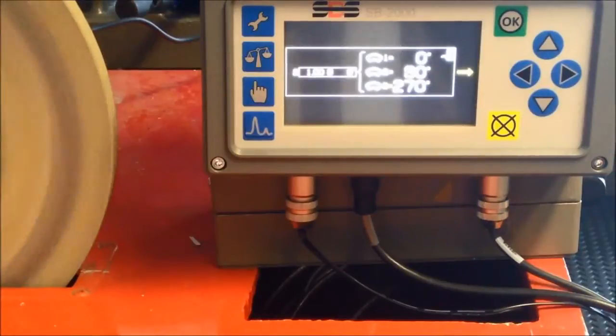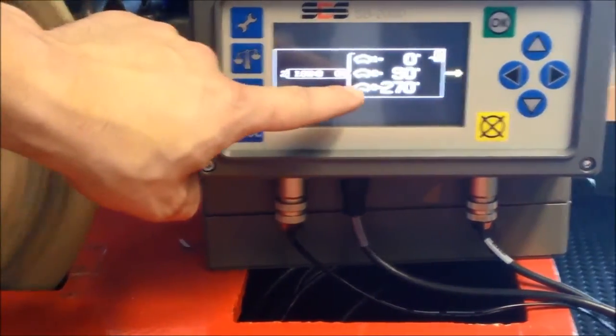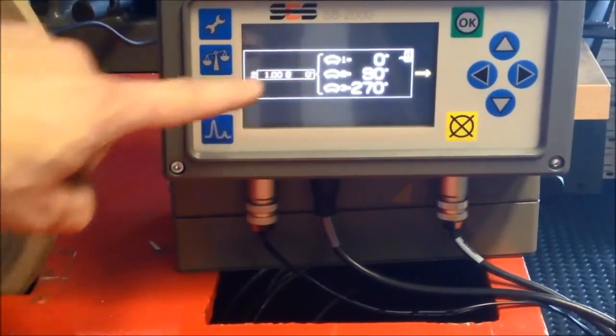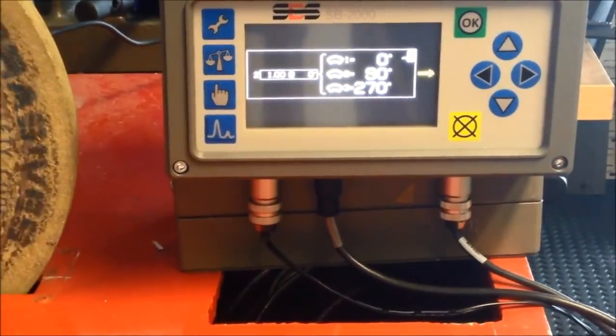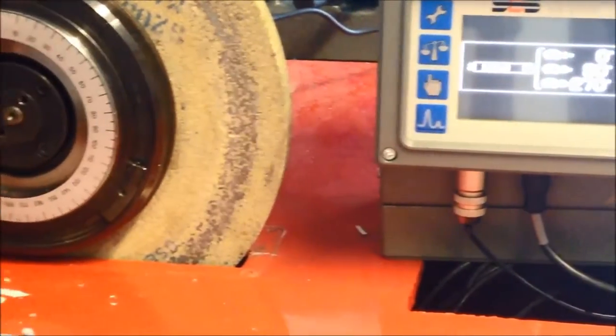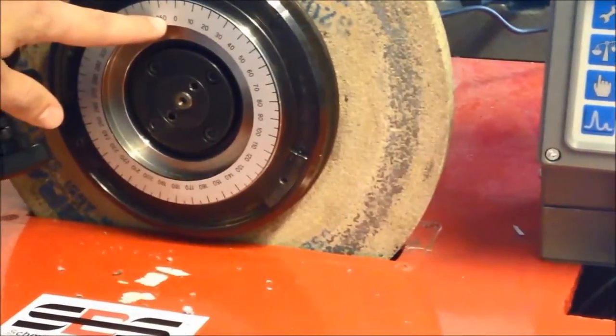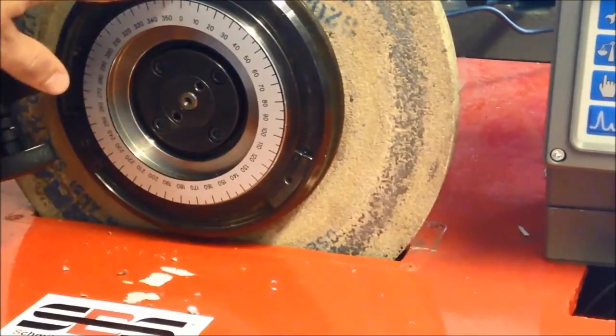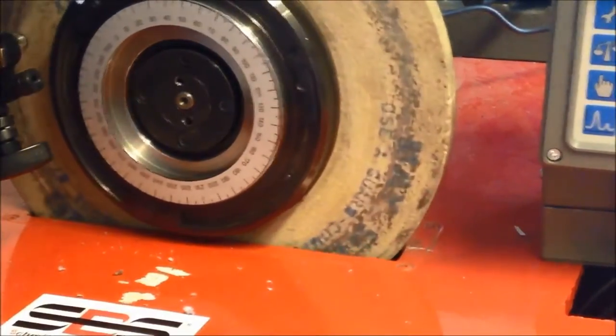Now the test phase. Position the weights at zero, 90, and 270 degrees. As we are using equal weights, it does not matter which weight goes in what position.